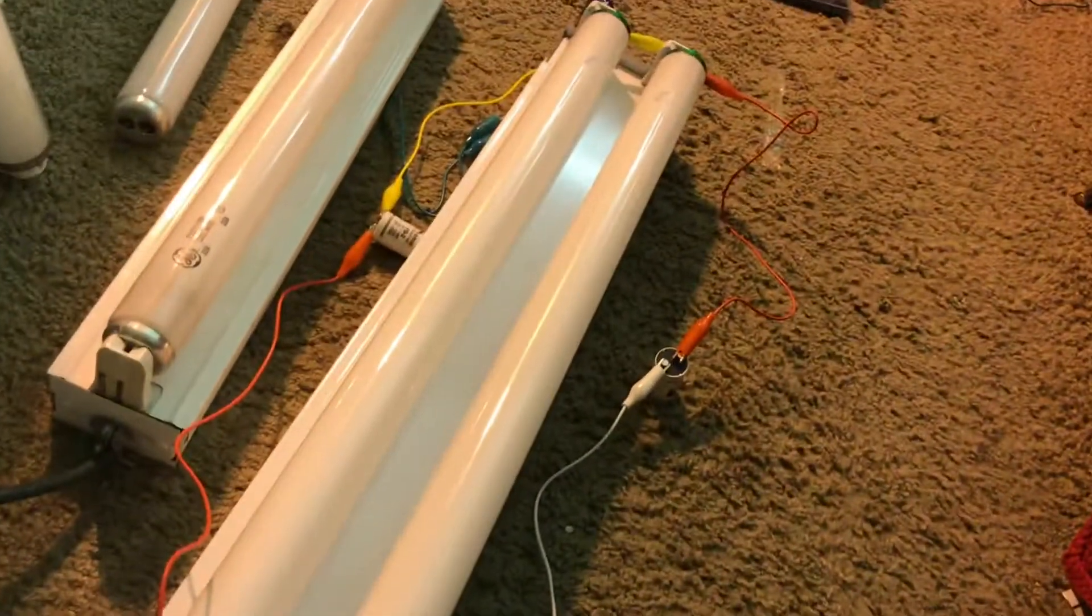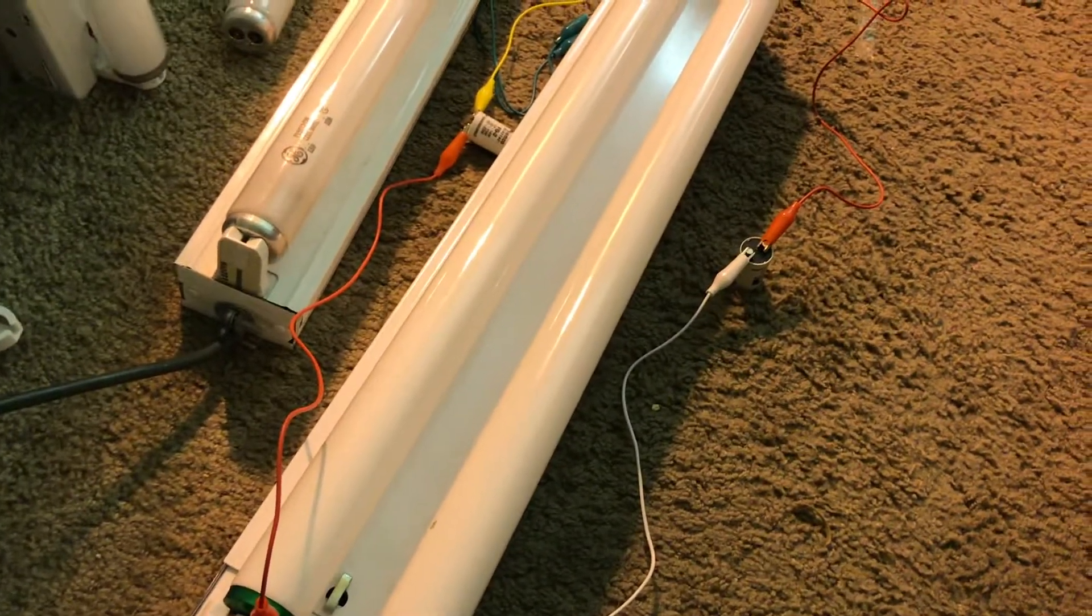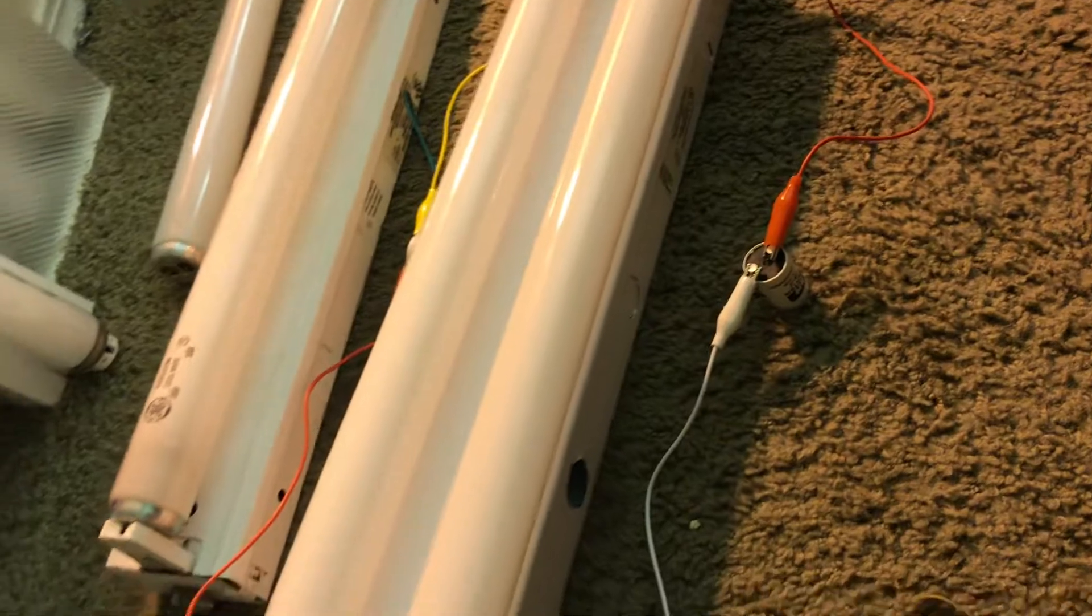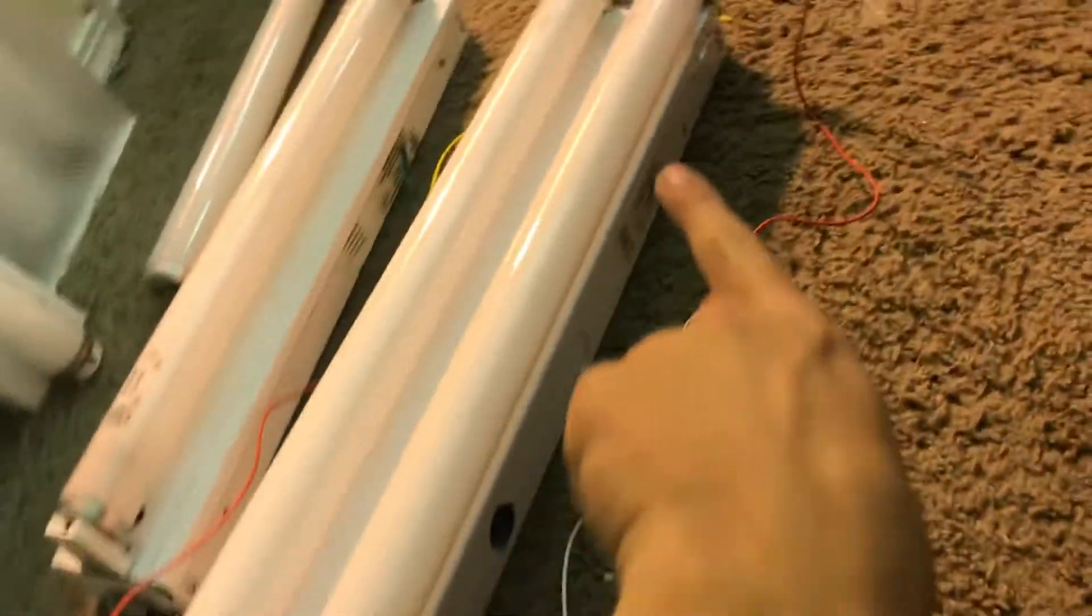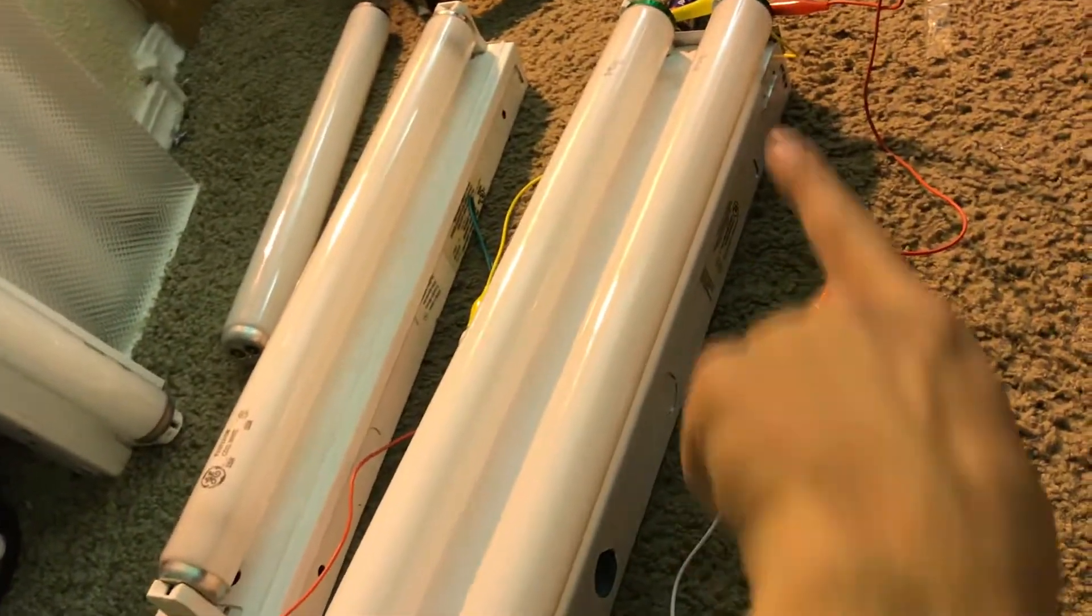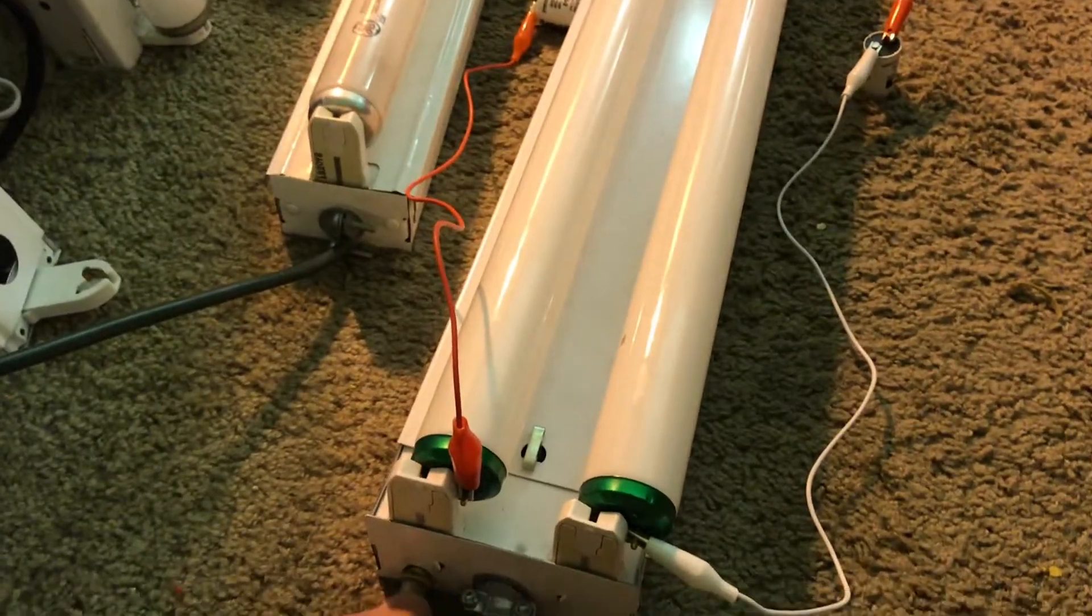Here we have a rapid start fluorescent light fixture and I have tapped starters onto them. So I remove one pin of each lamp and then I connect a starter between one of the pins on each end of the lamp. Now watch what happens when I flip it on.